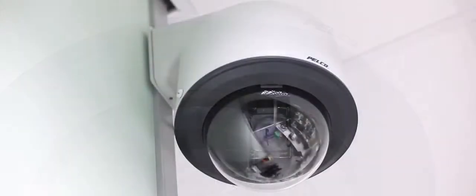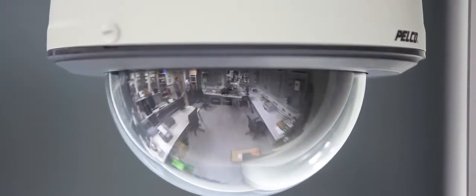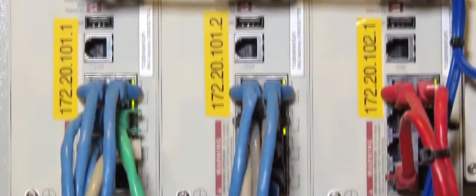Another aspect of data which is overloading our systems is video streaming, where it's quite interesting nowadays to be able to have a physical view of what's going on practically on the plant, but superimpose and synchronize that with alarm data. The big benefit of industrial Ethernet, as opposed to the proprietary systems we've talked about, is that it allows us to manage all these different data types and different media through different protocols on the same physical cable. As well as that, most importantly, with industrial Ethernet, we're able to manage and channel and route that data and prioritize that data so we're not overloading parts of the system that don't need to be overloaded.